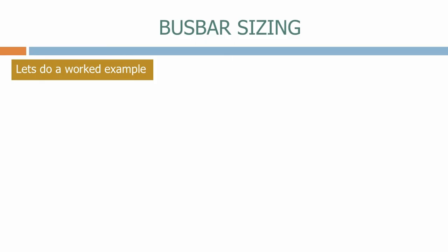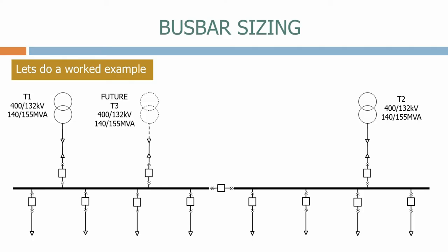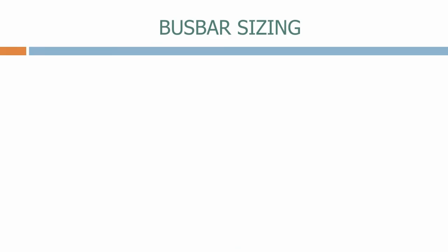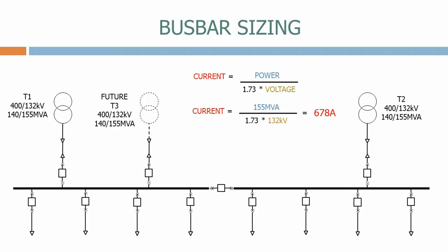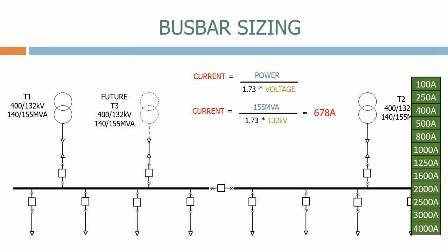Let's do a worked example. For the arrangement shown, calculate the ratings of the busbars and the current ratings of the incomer and busbar section breakers. First, let's work out the peak current produced by each of the transformers. The current equals the power divided by root 3 times the voltage. The current therefore equals 155 MVA divided by root 3 times the secondary voltage of 132 kV. Therefore, each transformer contributes a maximum of 678 amps. Each incomer circuit breaker needs to carry this current. Looking down the standard rating table for circuit breakers, we choose an 800 amp rating.